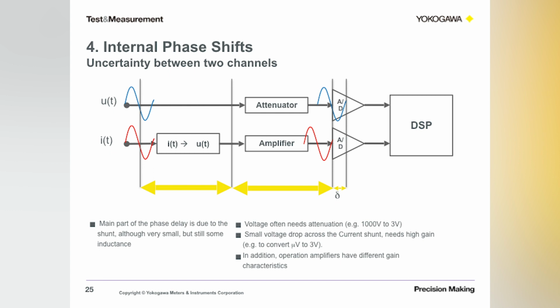To measure current, we need an accurate internal shunt on the front end. The voltage measured across that shunt is then passed to an amplifier in case a small voltage drop needs to be amplified for the A to D. On the other hand, the voltage measurement does not require a shunt, but may need an attenuator to bring that high voltage down to the A to D's measurable level. But you can see both signals have different obstacles in the path. Even though the signals are applied to the inputs at the same time, by the time they reach the A to D, there will be a slight phase shift between voltage and current as they both arrive at the A to D.